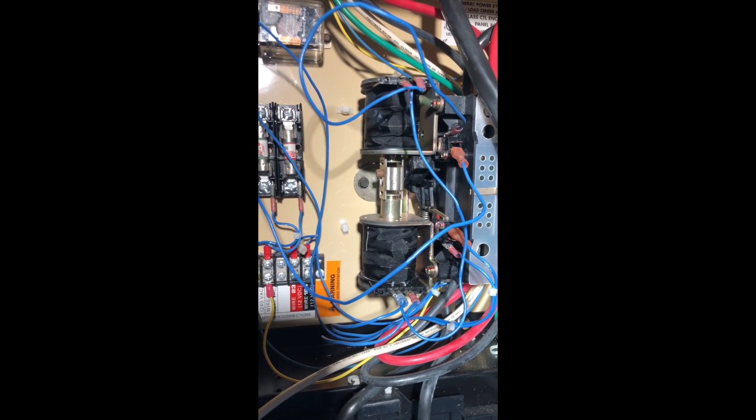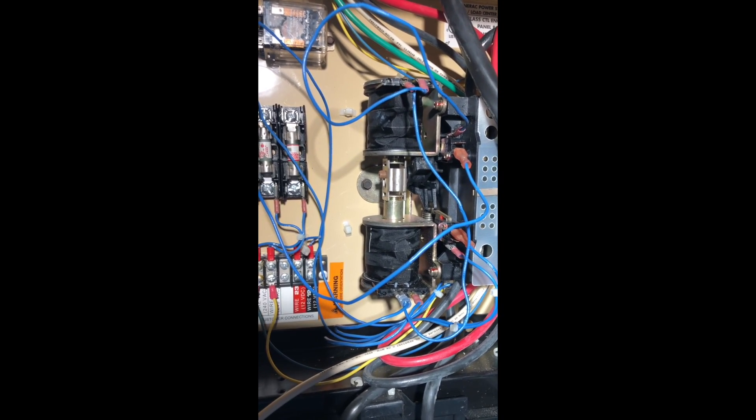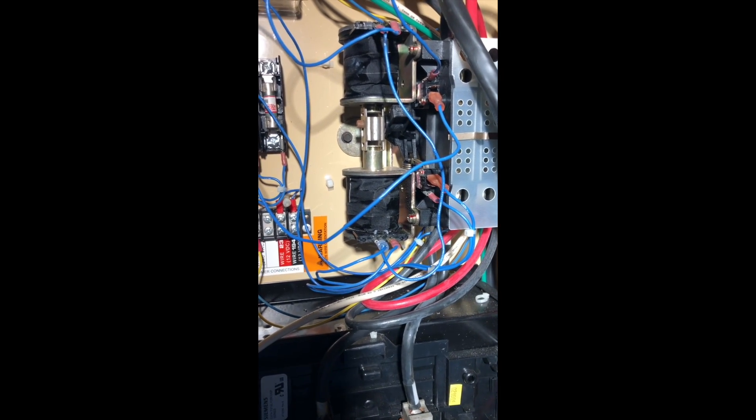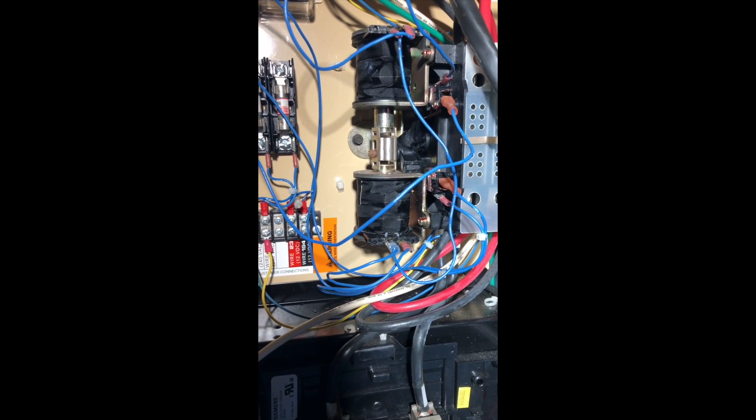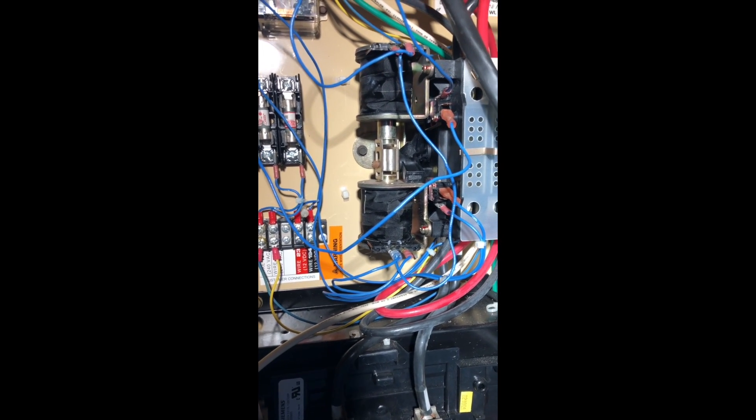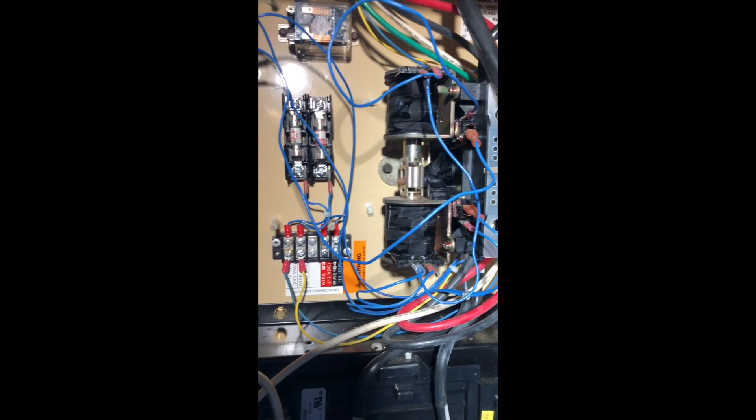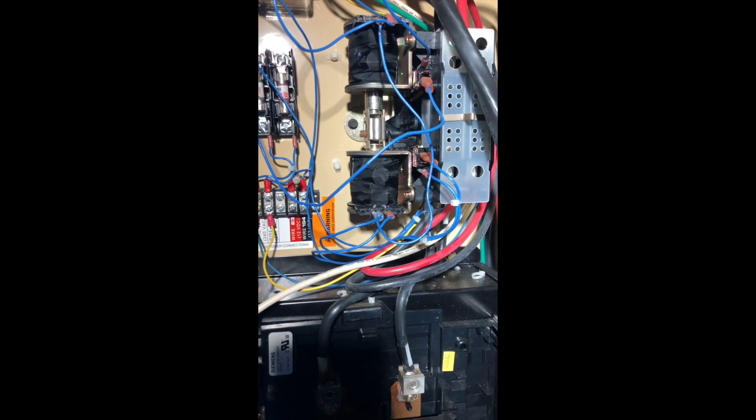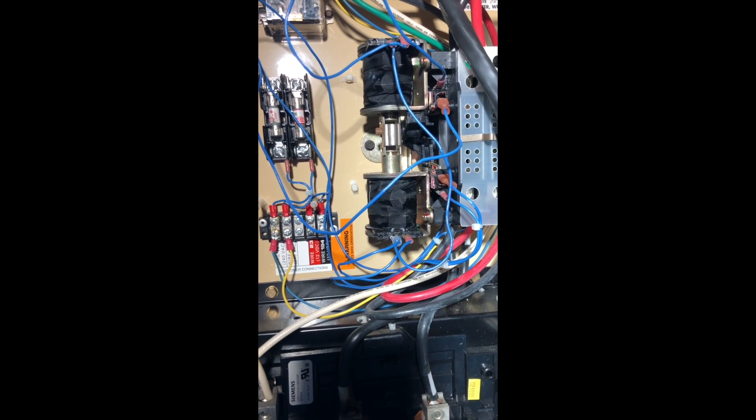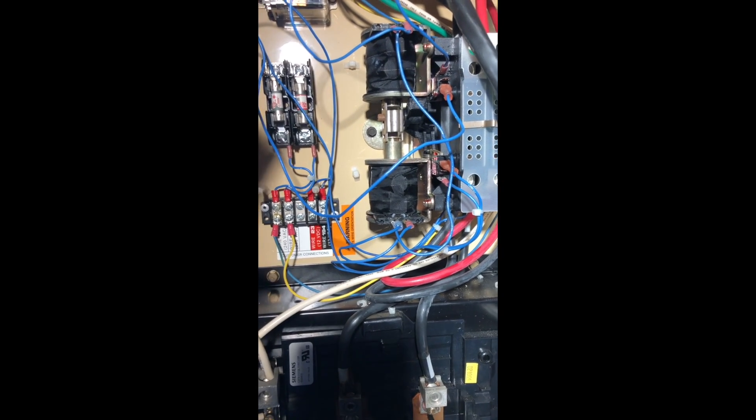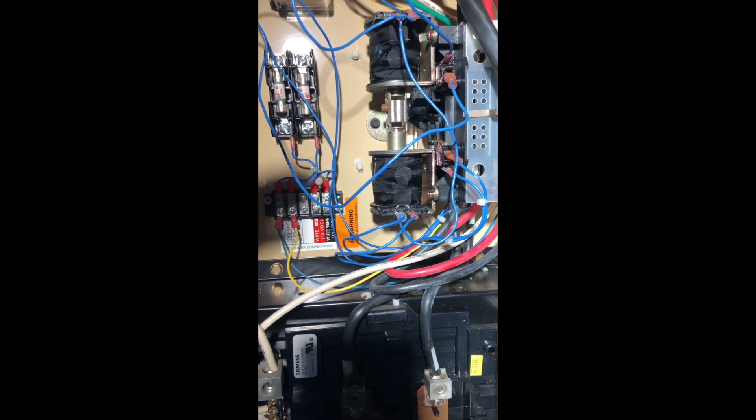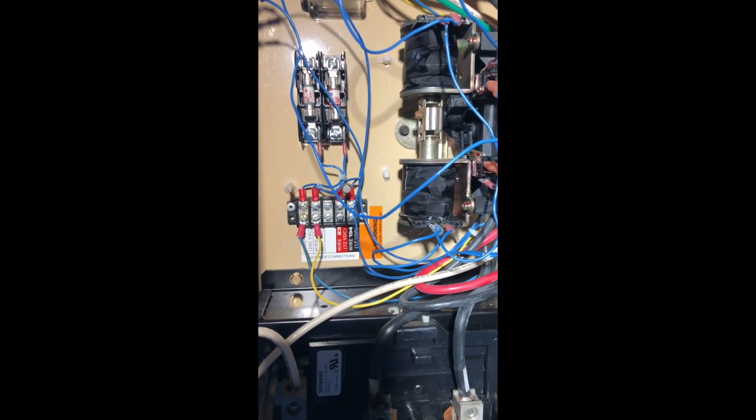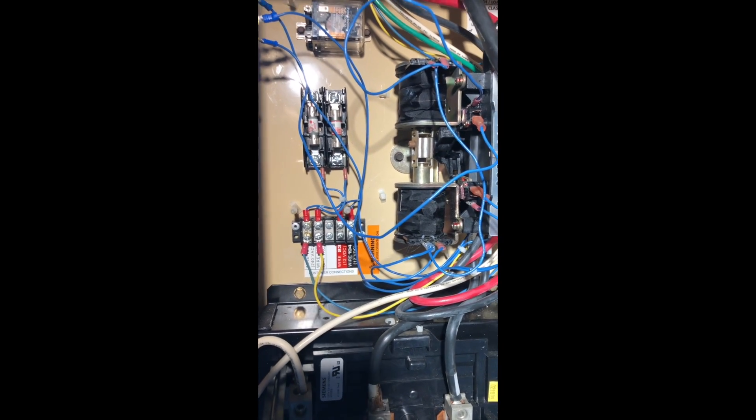And I can do that as long as I have power on the generator side. If I don't have power on the generator side and I need to get back to the house, I'm going to have to make that connection manually by moving that black lever. Not a big deal, but the way I'm going to do it now - we lose power, I'll fire up the generator, I'll come out here and flip the switch and we'll be on. And then if I need to go back to the house, before I shut the generator down, I will flip the switch, go back to the utility side, then I'll shut the generator off.